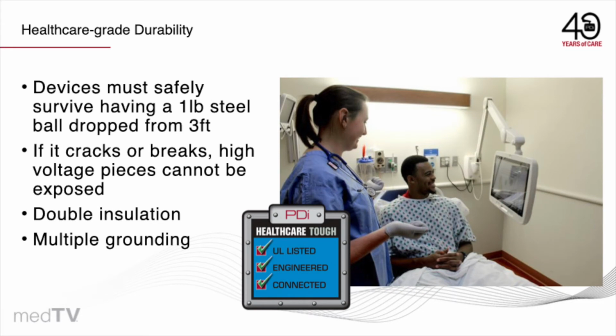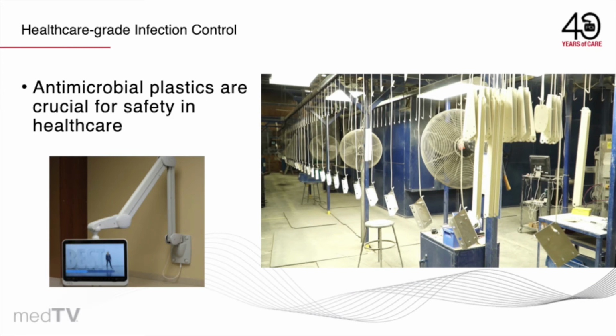It has to safely survive a drop of a 1-pound ball from 3 feet. So a steel ball is dropped on the device from 3 feet. It can crack, it can break. These things are glass, they're allowed to break. What you can't then do is touch any high voltage or voltage that can provide a shock to the patient. So another degree of double insulation or security there, multiple grounding. We choose to make all of our televisions out of antimicrobial plastic for the cleanliness and disinfection. Most of the time antimicrobial plastics are not used on a consumer grade product in the home environment unless it's something that's in the bath or in the kitchen. A consumer television doesn't use V0 plastic, doesn't use antimicrobial plastic, and doesn't have a double insulated or grounded plug.